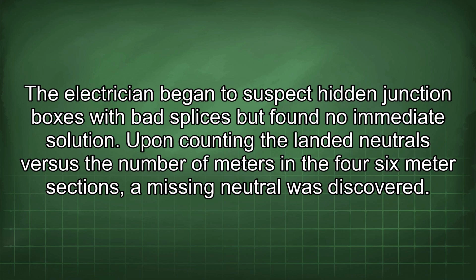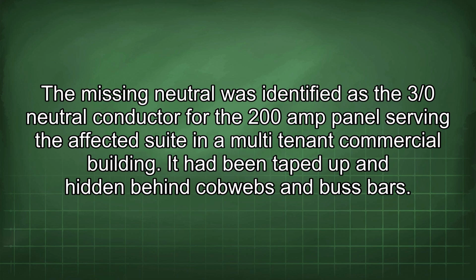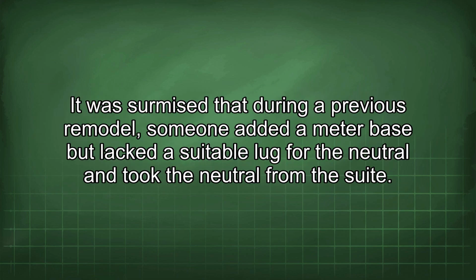Upon counting the landed neutrals versus the number of meters in the 4 6-meter sections, a missing neutral was discovered. The missing neutral was identified as the 3/0 neutral conductor for the 200 amp panel serving the affected suite in a multi-tenant commercial building. It had been taped up and hidden behind cobwebs and bus bars. It was surmised that during a previous remodel, someone added a meter base but lacked a suitable lug for the neutral and took the neutral from the suite.